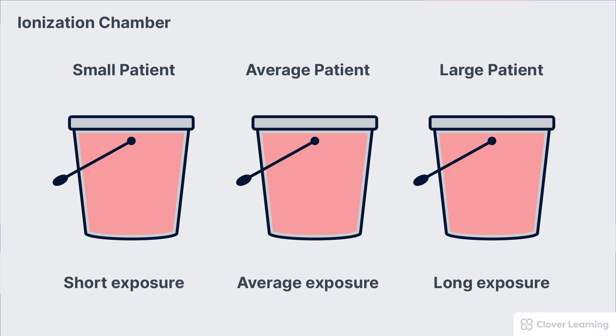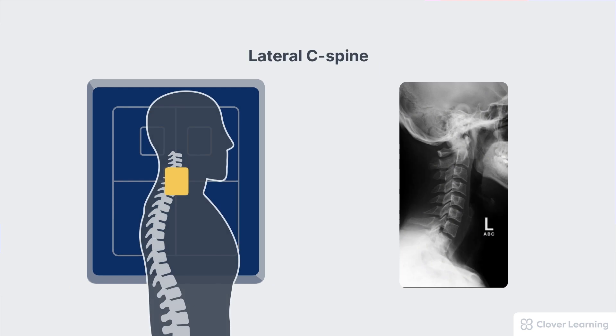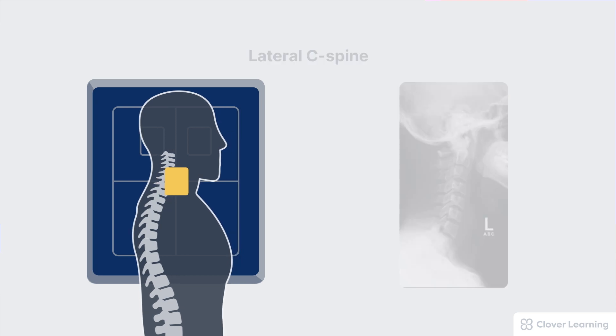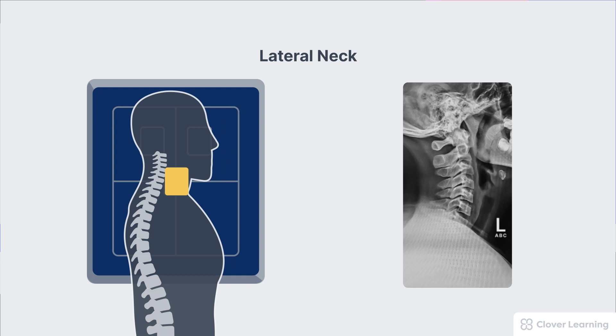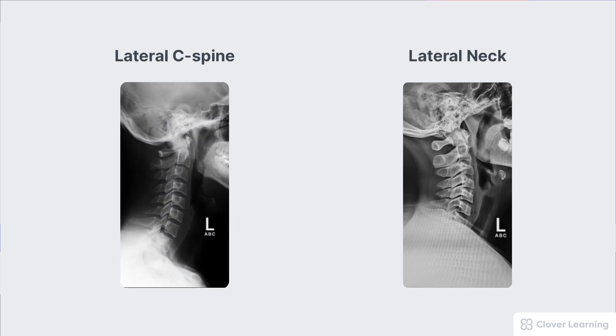In order for the AEC system to work correctly, you have to select the correct cells and position the patient correctly over the cells. The part of interest should always be placed directly over the ionization chamber. For example, when performing a lateral C-spine, the C-spine should be centered directly over the center AEC cell. When the center cell is activated, the C-spine will be perfectly exposed. A common mistake is to center anterior to the spine, with the soft tissues of the neck over the AEC cell. This results in a perfect exposure of the soft tissues but underexposure of the spine.